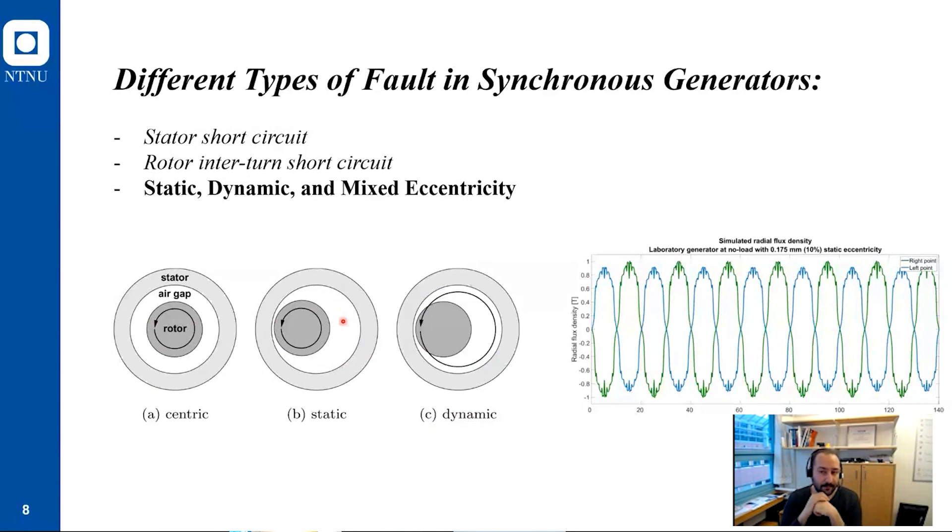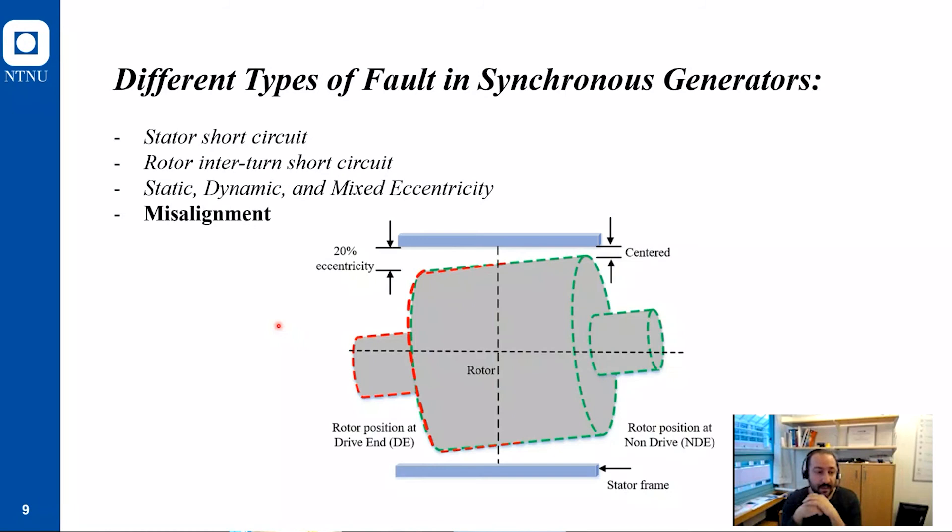The third type of fault is eccentricity faults. The machine, the rotor, is supposed to rotate exactly at the center of the machine. But when we have a static or dynamic eccentricity fault, the rotor is closer to the stator, and in the worst case it could touch the stator and the machine will stop. The other type of fault is misalignment. It's a combination of static and dynamic eccentricity fault, but the rotor in an axial direction is also tilted. This fault is kind of a worse type of static and dynamic eccentricity fault.